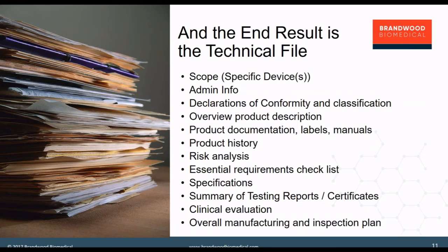And obviously, the clinical evaluation report should be included and maintained within the technical file for currency. So again, it is a regulatory requirement to produce a clinical evaluation report. This is actually one of the items included in your essential requirements checklist. So it will be an expectation that this primary piece of evidence is also included in your technical file. So this is the foundation of safety and efficacy for your product. It is critical to include that in your technical file.